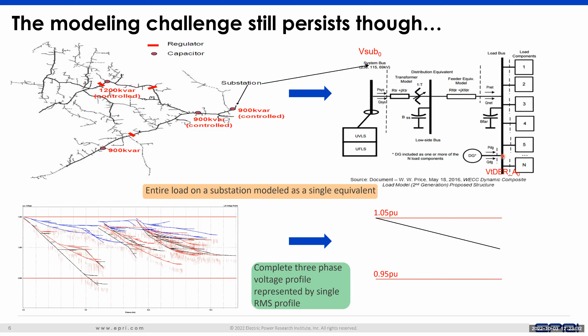So in an aggregated fashion, when you have an aggregated model such as this, wherein the entire DER is placed as one model, and all it is going to see is only one voltage, which is at this bus, we need a mechanism to capture the fact that a certain percentage of the DER may trip and a certain percentage of the DER may not trip. And that is what these blocks do in the model. And again, there's more description on it in this reference.